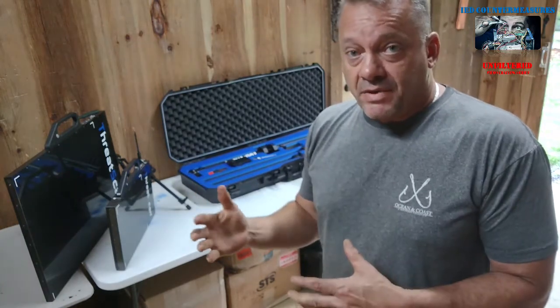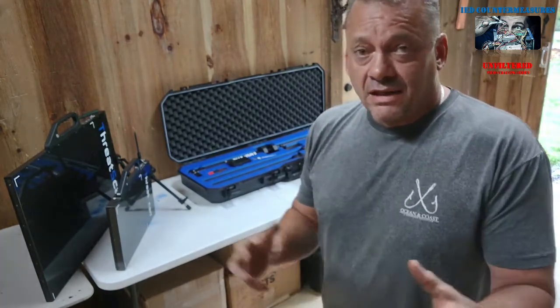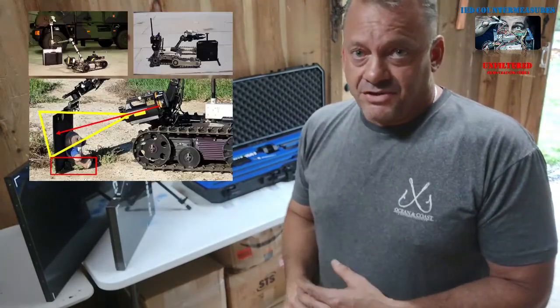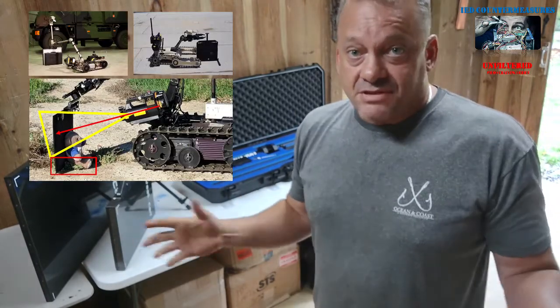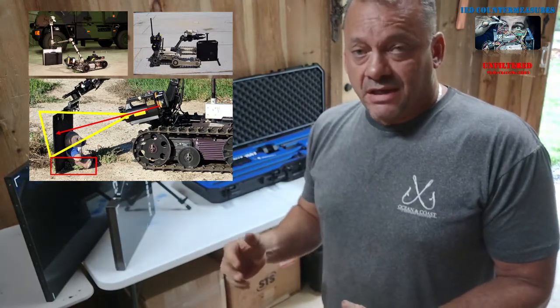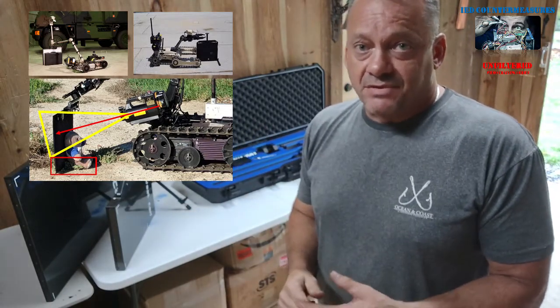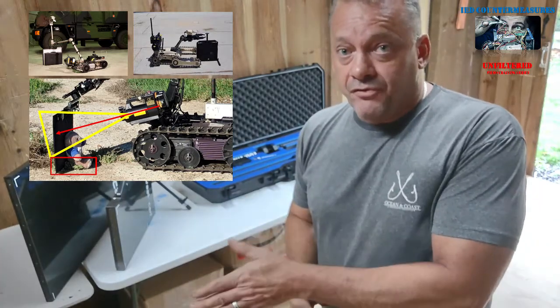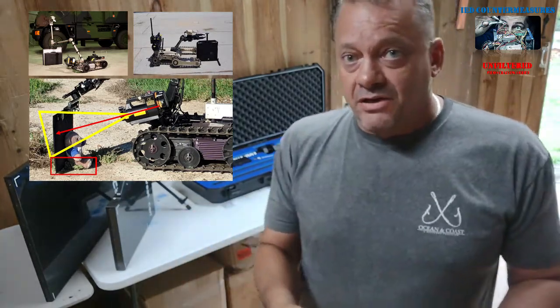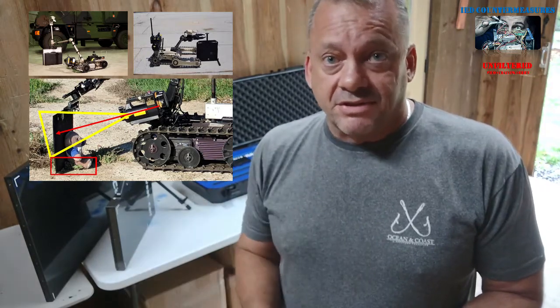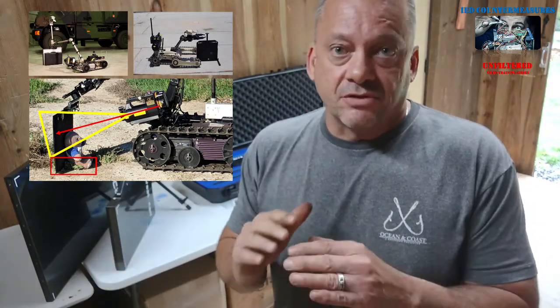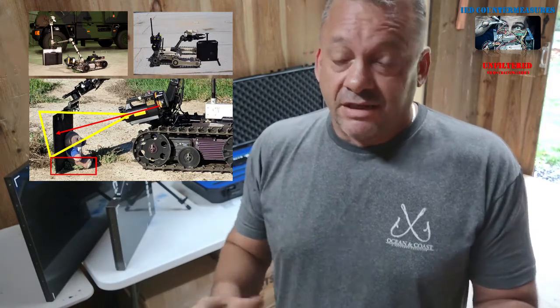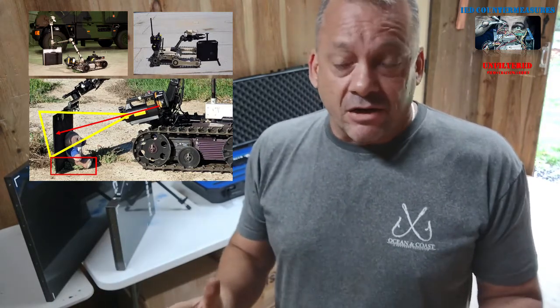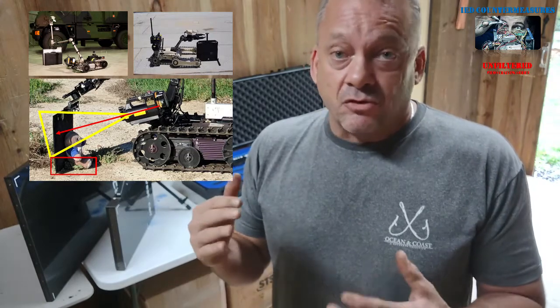I've done videos before about how you can get cutoff in your image based on your generator height. A lot of the robot C-arm configurations you see mount the generator to the chassis. That's absolute crap, it doesn't work. It limits you to ground scans only, and it actually makes the lower edge cutoff massive. If you see any vendor offering a robot X-ray integration where the generator is mounted to the chassis, don't buy it, it's a complete waste of your time. They're shit, they don't work, they're a nightmare. They only do ground scans, and they do ground scans like shit.